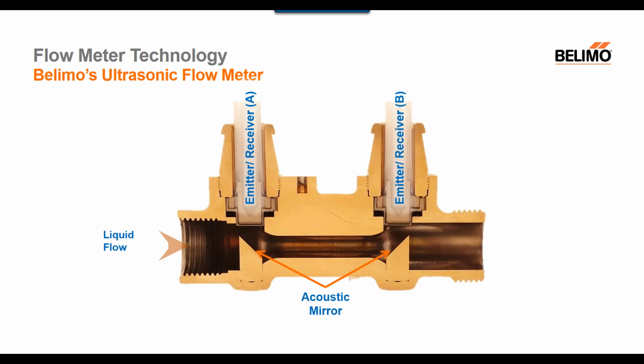The ultrasonic flow sensor relies on the use of two ultrasonic transmitters and receivers. Two acoustical mirrors are used to reflect the signal within the pipe. There is also a temperature sensor integrated into the flow sensor housing. This is used in the logic to compensate for water temperature changes and also to calculate glycol concentration.